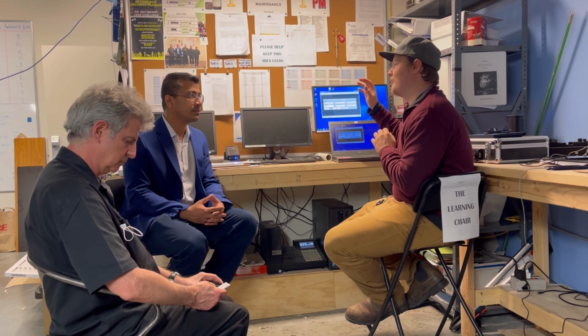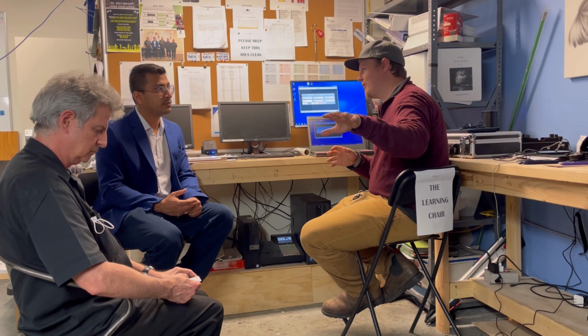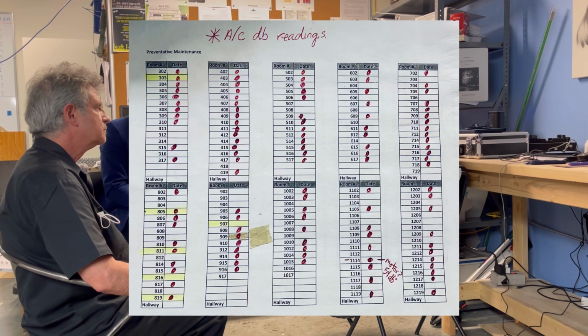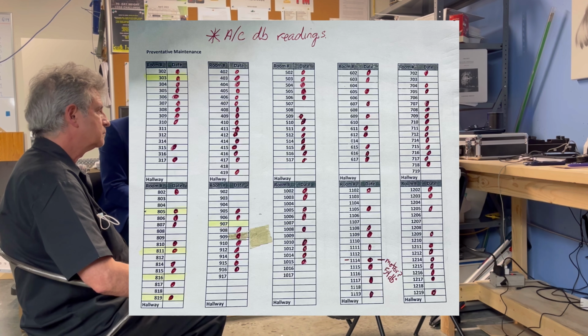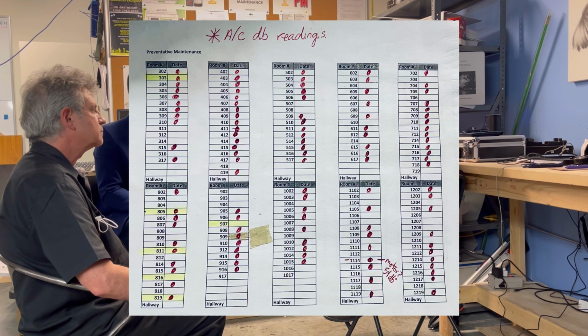If these are heat recovery systems, they'll have heat recovery boxes—basically a branch box that serves multiple fan coils. From our outdoor units we come down to a branch box, which separates into probably 4 branches depending on the age of the job, feeding 4 units off that one branch box. So the noise could be specific to a group of 4 units, to an entire system, or to a single fan coil. The more information you can gather about how many systems are making noise, and whether they're tied together or isolated, the better.